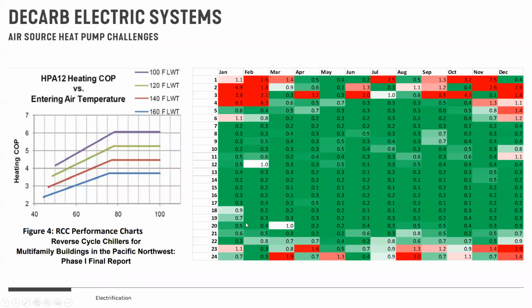But notice that if I'm trying to heat a building, I'm often doing it during these hours: January, December, February, midnight to 5 a.m. Those are the hours I generally need to provide heat, and those are the same hours a heat pump may be less efficient. So from an engineering standpoint, we're working hard on what we call load shifting—trying to move energy use around so our heat pumps can operate during the prime middle hours and store energy for later use in the evening.